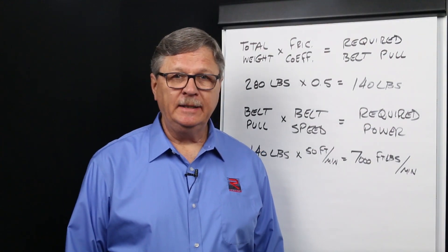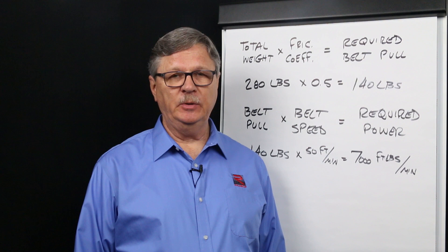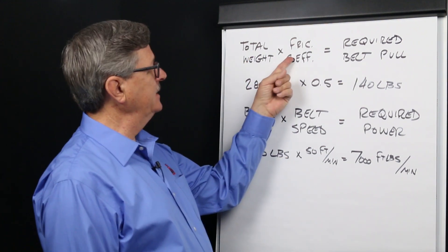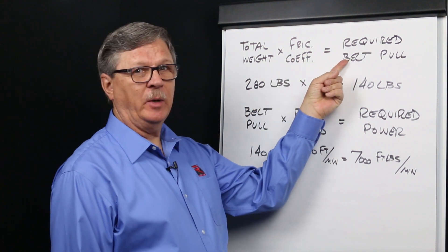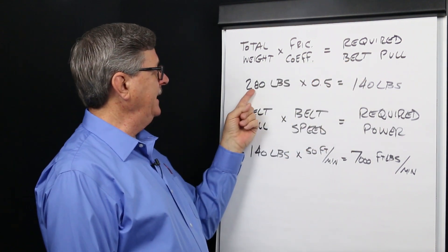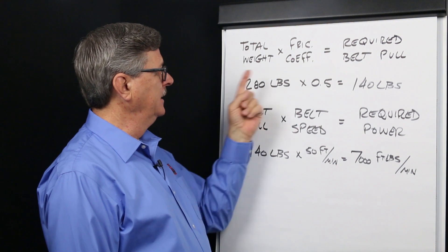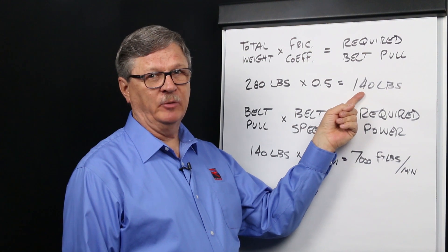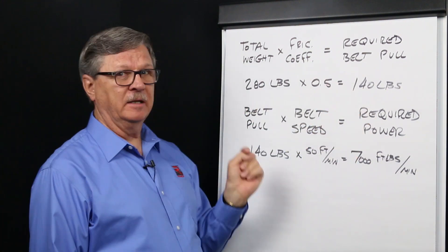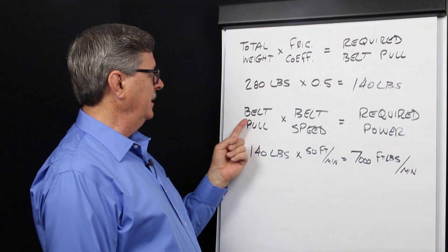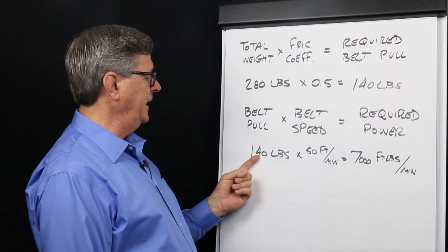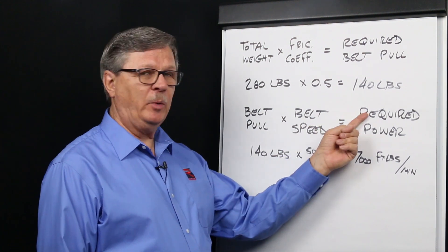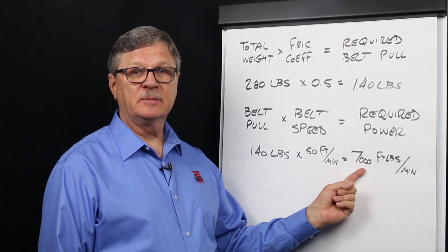Since the total weight times the frictional coefficient equals belt pull, we can now calculate required power. Total weight times frictional coefficient equals required belt pull. 280 pounds of total load times a frictional coefficient of 0.5 equals a belt pull requirement of 140 pounds. Now we can convert this to power. A belt pull of 140 pounds times a belt speed of 50 feet per minute equates to a required power of 7,000 foot-pounds per minute.